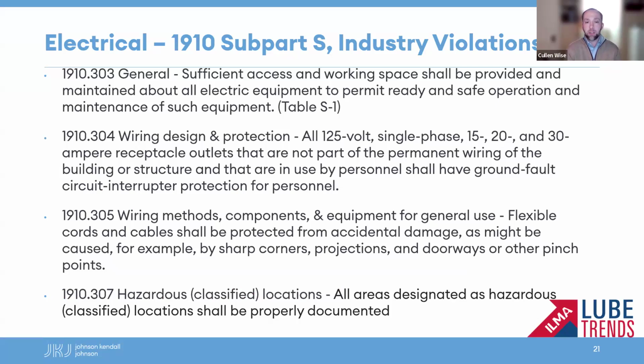1910.304, wiring design and protection, says that all 125 volt, single phase, 15, 20, and 30 ampere receptacle outlets that are not part of the permanent wiring of the building or structure and that are in use by personnel shall have ground fault circuit interrupter protection for personnel, GFCI protection. So it was a temporary setup, not part of the permanent wiring, and it did not have GFCI.